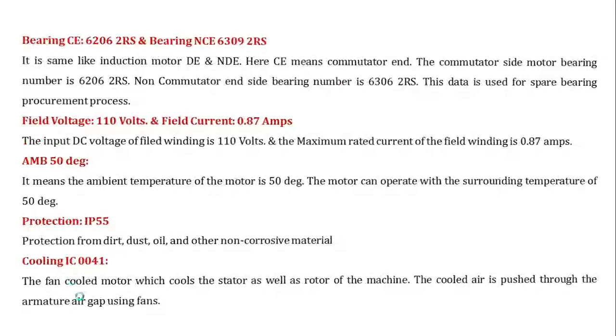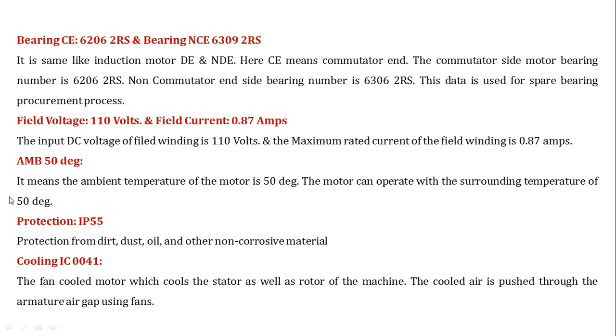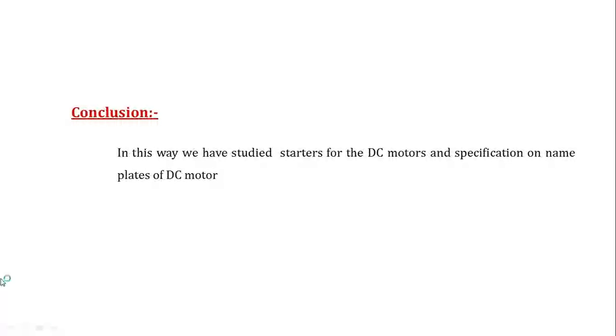So these are some standard details which are printed on the nameplates of the motor. Then bearing CE, it is the same as in an induction motor, that is DE and NDE. Here CE means the commutator end, and the commutator side motor bearing number is 6206 2RS. The non-commutator end bearing number is 6306 2RS. These are the standards mentioned here. Then the field voltage and field current. Then protection from dirt, dust, and other non-corrosive materials. Then cooling IC, a fan-cooled motor which cools the stator as well as the rotor of the machine, is also mentioned here. So these are some important parameters mentioned on the nameplates.